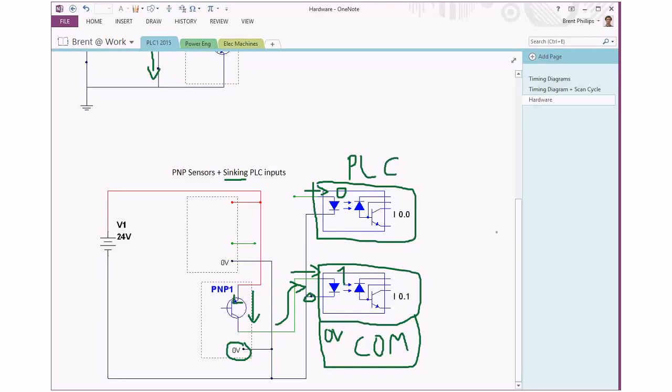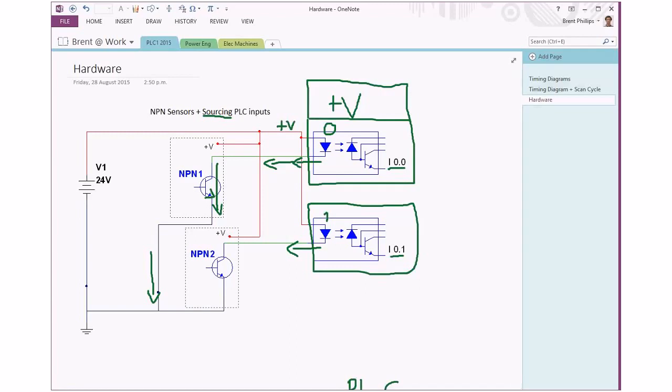If we look back up here, this is our sourcing PLC, and each of the numbered terminals here has the current flowing out from the PLC. In this case, the PLC itself is acting as a source for that current. It's the easiest way to distinguish it - once you know the current direction, then you know you have to have a positive voltage for your common. Hopefully that helps with remembering the difference between sinking and sourcing for PLC inputs and learning about NPN and PNP sensors.